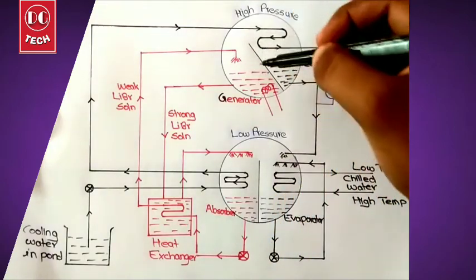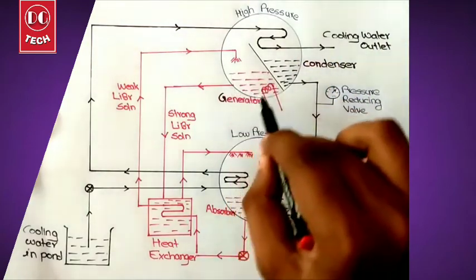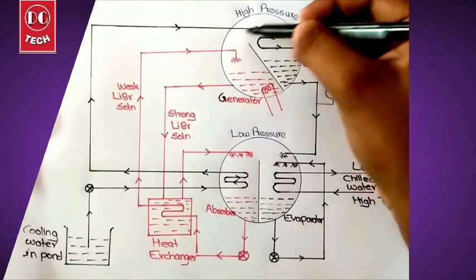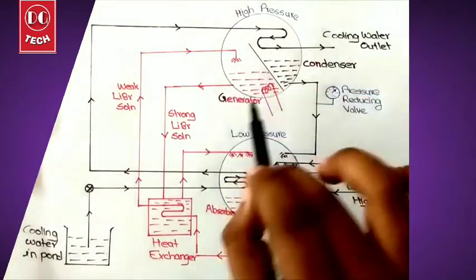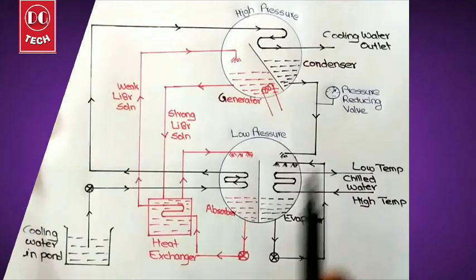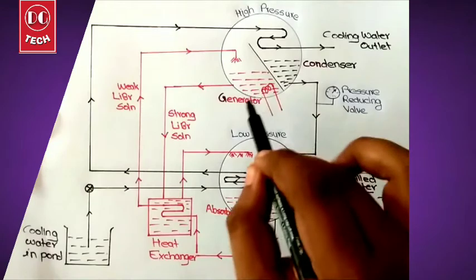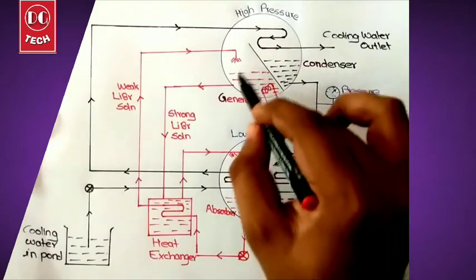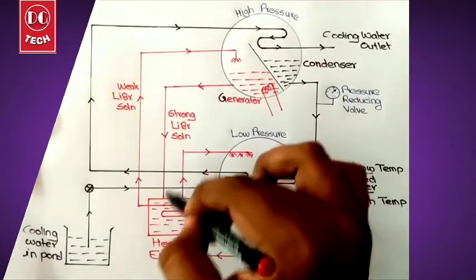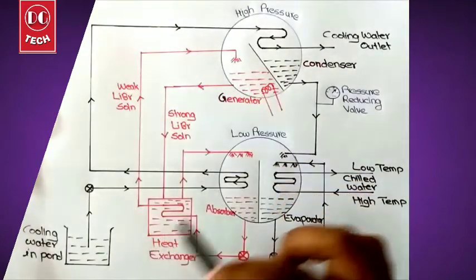Since the boiling point of water is less compared to that of lithium bromide, water will get evaporated and only water moves towards the condenser. The rest of the liquid will be only lithium bromide—all the water evaporates, leaving strong lithium bromide. This strong lithium bromide flows through the heat exchanger, where heat is absorbed by the incoming weak lithium bromide.